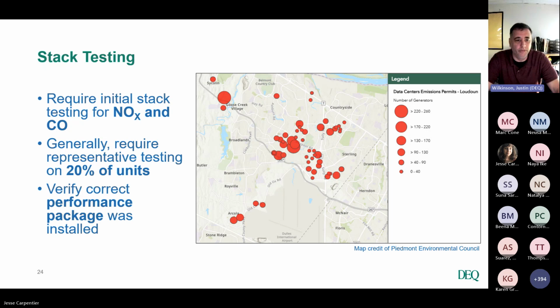We are looking at a representative sample from each one of the makes and models out at the facility. And I will just say that we don't see many failing results from this, at least above and beyond what the manufacturer's recommending. Where we might see some failing results is if the units are not set up properly, if they have installed the wrong performance package on the unit, where they're going with a fuel efficient package instead of a NOx efficient package. Those are some of the reasons why they're not meeting their emission limits in the permit.